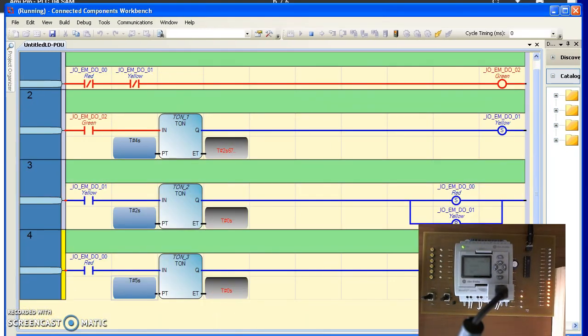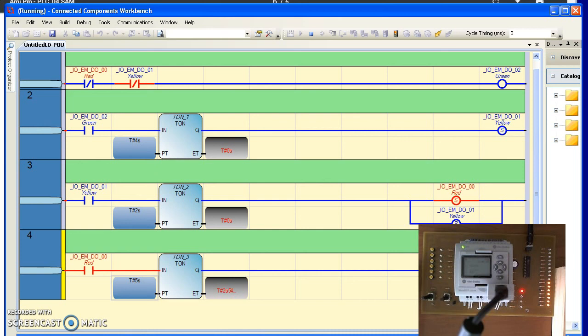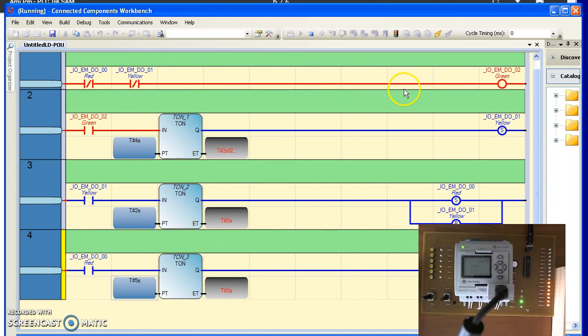So here's the stoplight. State transition logic does work for stoplights, but it's an absolute bear. Using timers, it's much simpler. Here, if you're not red and not yellow, you've got to be green. That's the default.